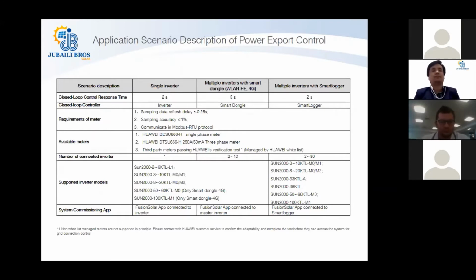Now, these power meters must have some specifications. Let's say the refresh delay should be less than 0.25 seconds, and the sampling accuracy should be less than 1%. Communication should be in Modbus RTU protocol, which is one of the basic requirements for any power meter to communicate with the Huawei smart logger. In the Huawei smart logger manual, you will find this list of power meters, and within those, a few would have the feature to be used for zero export control. Many of them are just used for reading the data, but cannot be used for zero export. But there are a few of them which you can use for zero export.